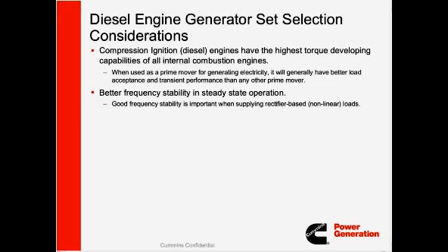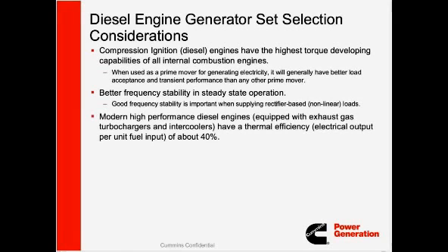The other thing is thermal efficiency of the power supply system. Modern high-performance diesel engines equipped with exhaust gas turbochargers and intercoolers have a thermal efficiency, which is electrical output per unit fuel input, of about 40%. This is higher than natural gas or spark-ignited gensets, which run at about 30 to 33% thermal efficiency. So as of now, diesel gensets have a higher thermal efficiency than equivalent natural gas generator sets.